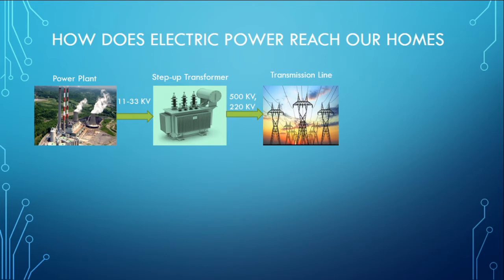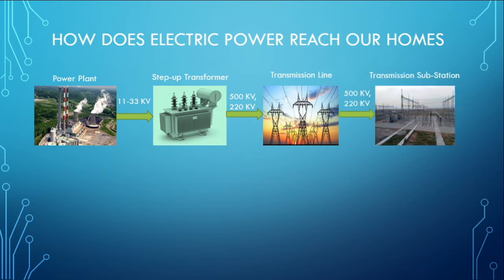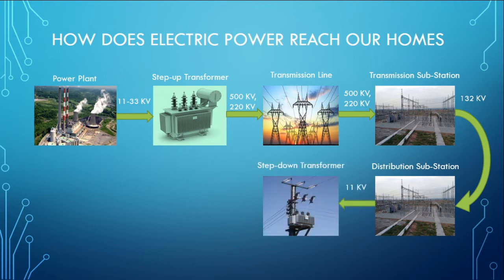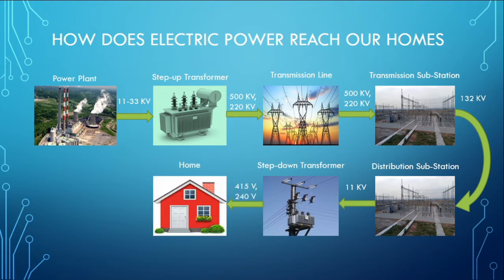The electric power is transmitted on high voltage transmission lines, which are then fed to a transmission substation. The transmission substation steps down these voltages to 132 kV, which are then fed to a distribution substation. The distribution substation further lowers the voltages to 11 kV, which is fed to a step-down pole transformer. These are the transformers that we see in the streets. This pole transformer further steps down the voltage to 415 V or 240 V, which is finally delivered to our homes.